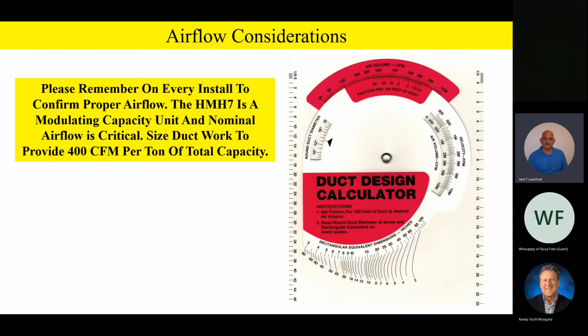Now, one of the reasons I like to stress this a lot, fellas, is the fact that this HMH7 has, I believe, 5 sensors on it. And it's looking at outdoor air temperature. It's looking at discharge line temperature on the compressor. It's looking at liquid line temperature. It's looking at suction line temperature. I believe there's a suction pressure transducer in there, so it's actually calculating superheat. The point I'm making is this: the outdoor unit has to have proper airflow on that indoor coil.